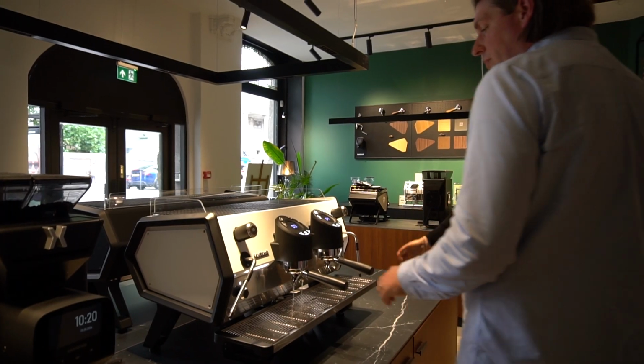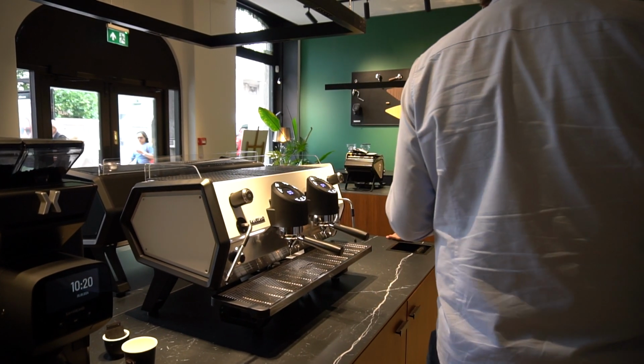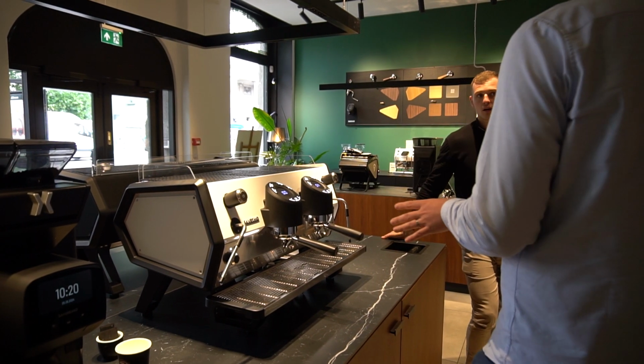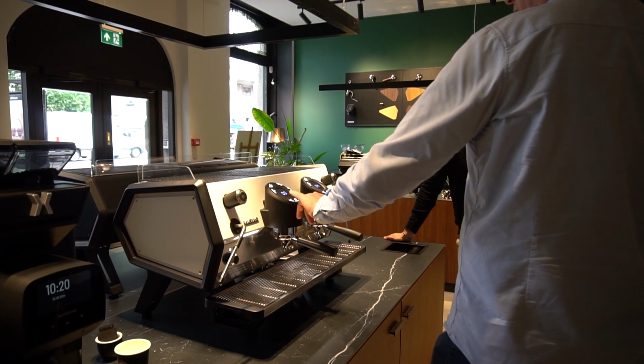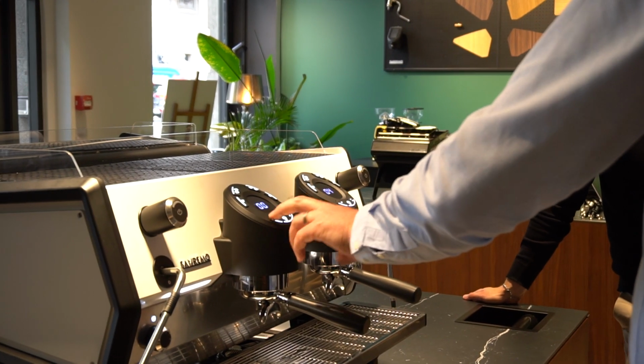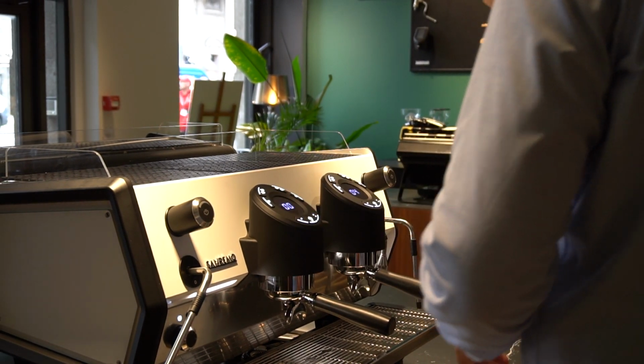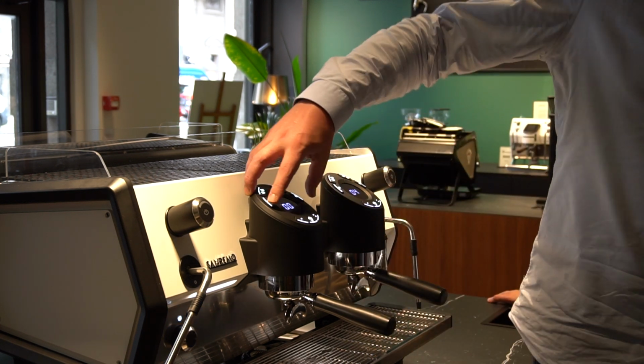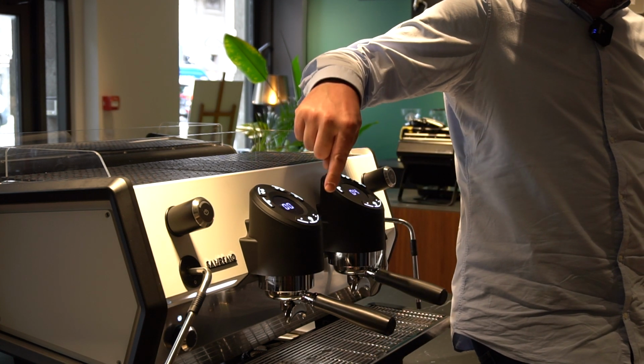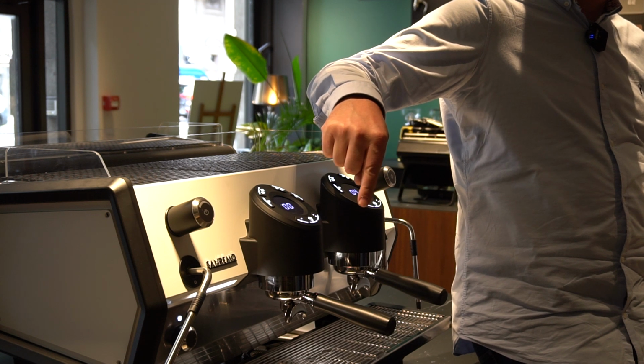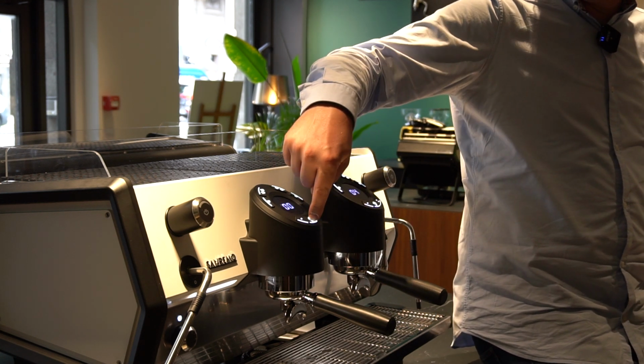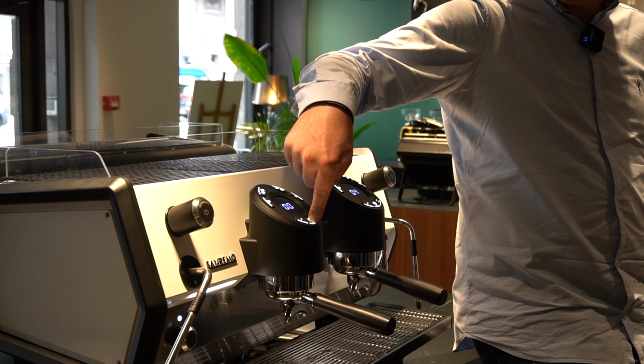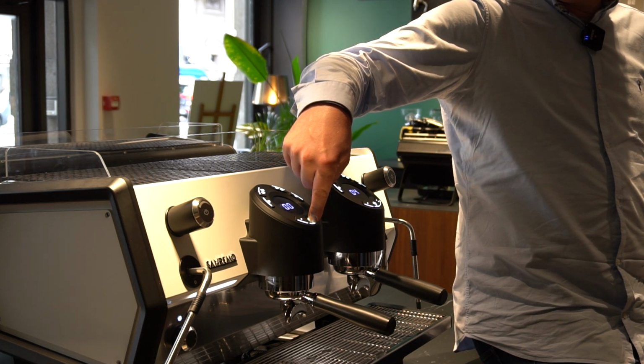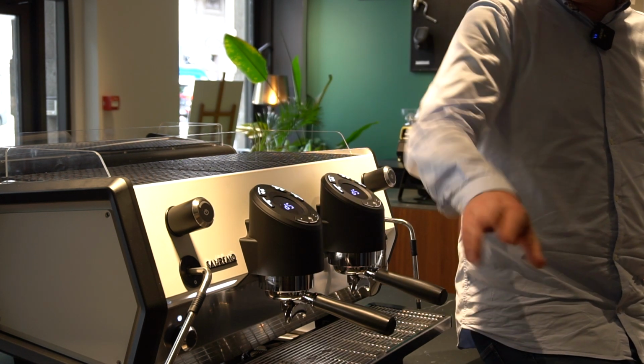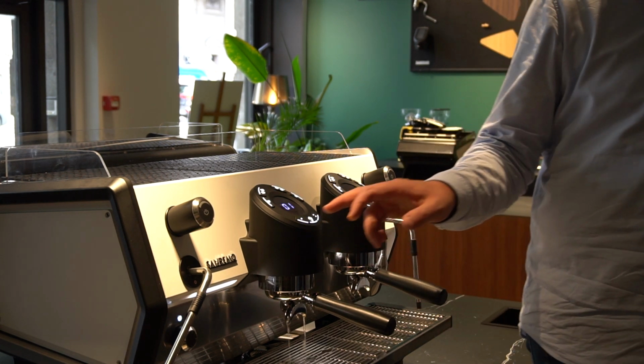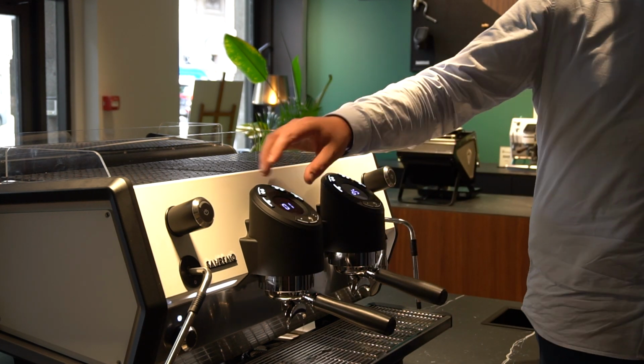So you have the option for 5 buttons or 7 buttons. Generally, we stick with 5 because there's no point in the others, so these two are pretty much disabled on UK models. I can turn them on if you want me to, but you've got 5 buttons as standard. You have your 4 recipes around the top, and then flush or a double press for a free flow, and settings. It sets exactly the same as a Zoe. Press and hold and then dose select, exactly as you would set on a Zoe. And left group programs, right? Yep, and then if you program that one, it's standalone.